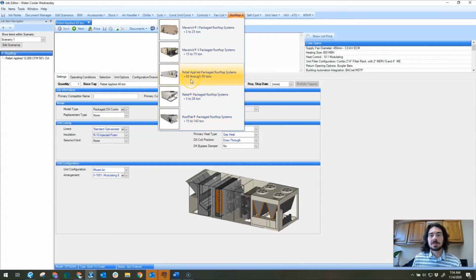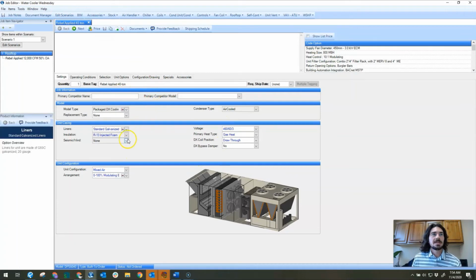In this case, we're doing a Rebel Applied, and we're going to shoot for a 40-ton selection. We've already got it started here. So we can choose different liners, voltage, gas type. In this case, I'm doing our heating type. In this case, I'm doing gas. DX coil position, we can do draw through or blow through.